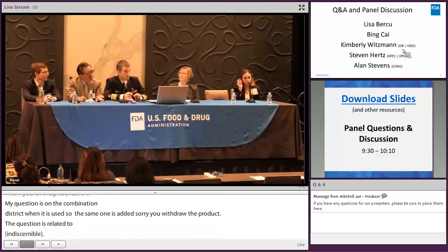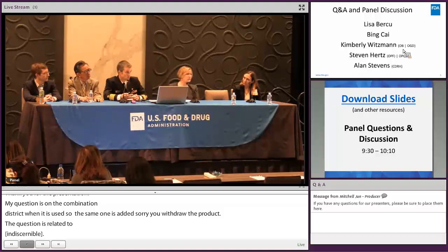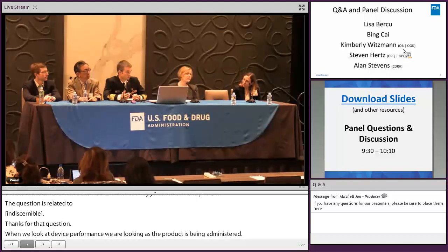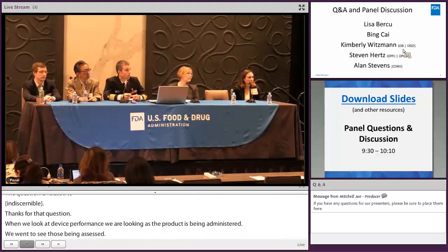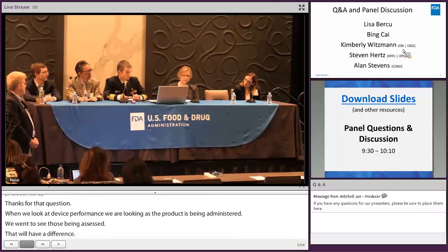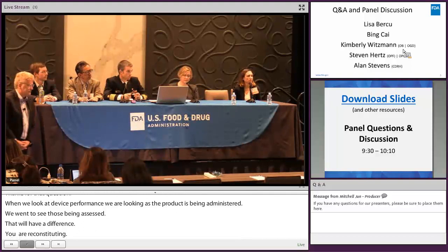Yeah, thanks for that question. When we're looking at device performance, as the product is being administered, we would want to see those EPRs being assessed at that point, if the actual reconstituted product is going to have a difference. But the breakout is already over because you have already transferred the diluent to the vial, so doing it in the same syringe doesn't make any sense. Right, yeah, so you're reconstituting and using the same syringe to administer. We would want that testing to be done as it would be administered to the patient. Thank you.